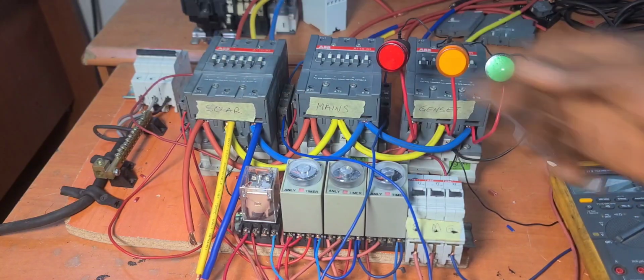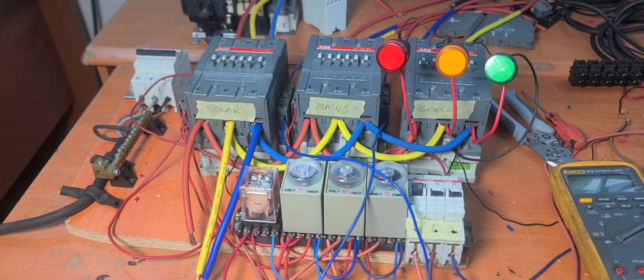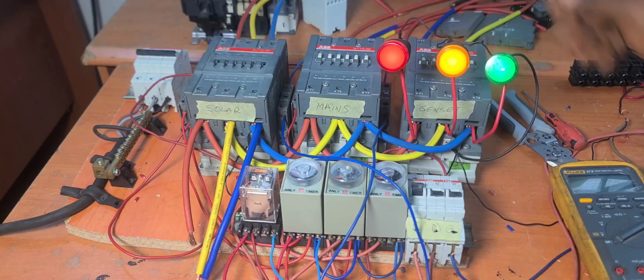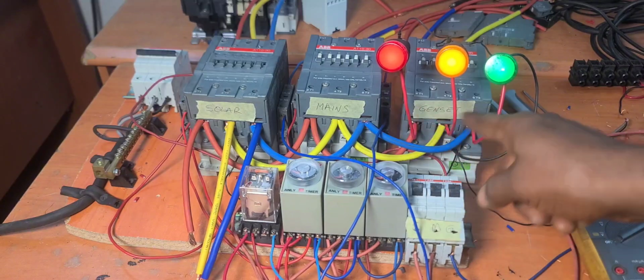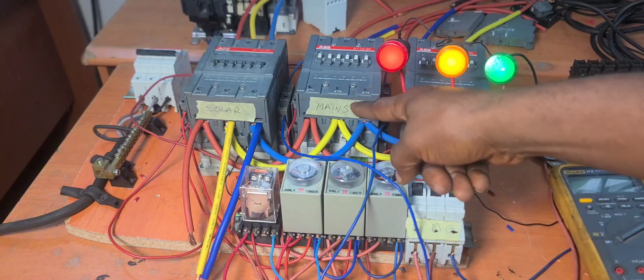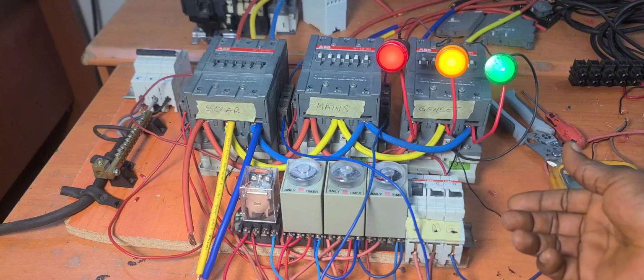And to demonstrate that, let us start with solar. If we energize this solar, it delays for some seconds and it connects. And now we have the three phases on our load. So what that means is that when this solar is on, this one cannot work and this one cannot work. Even if we put the switches on to send these signals to these two sources of power, like this simulates that mains is available and genset is available. All right. So you see that these two will not work.